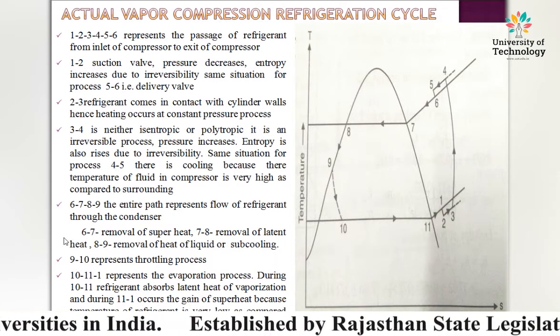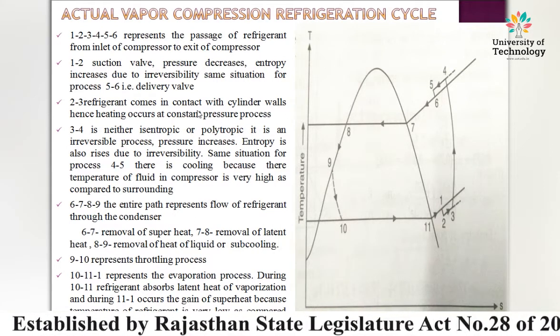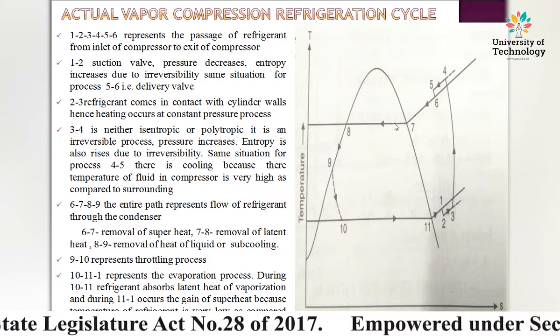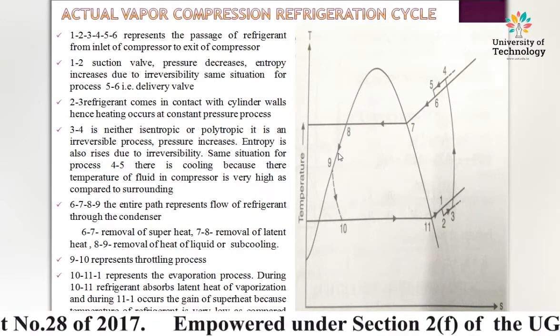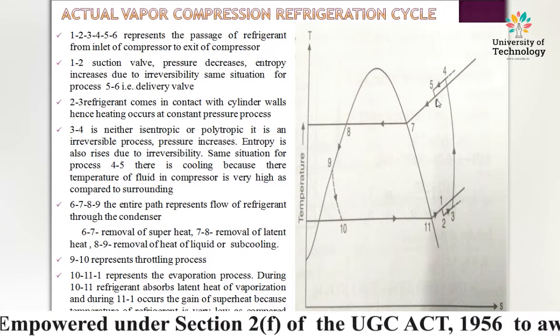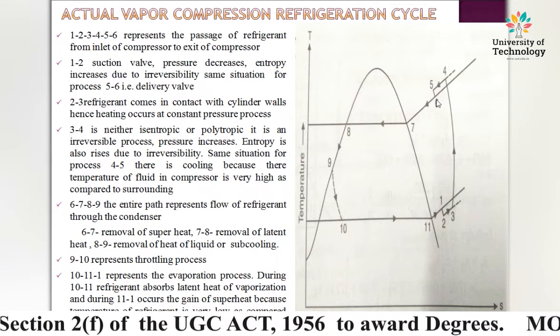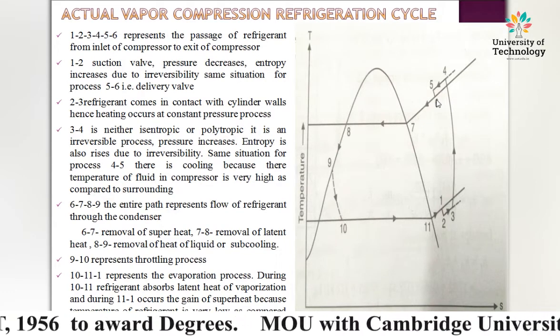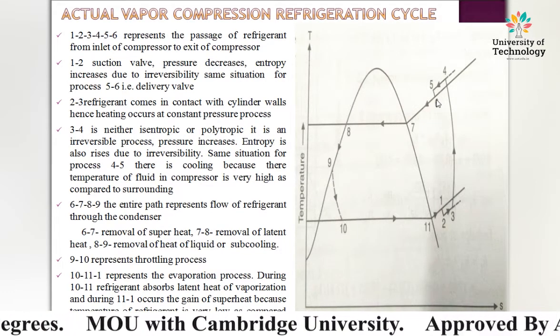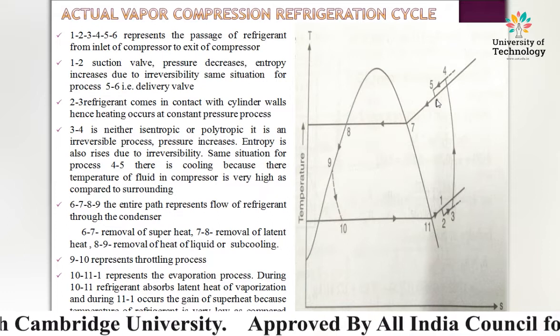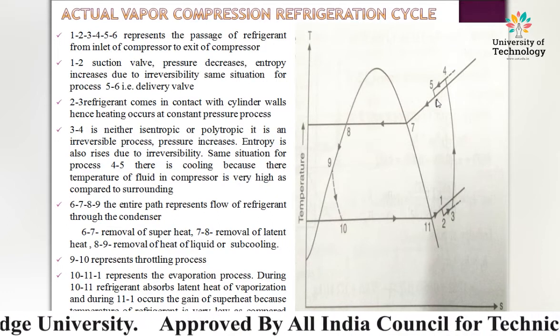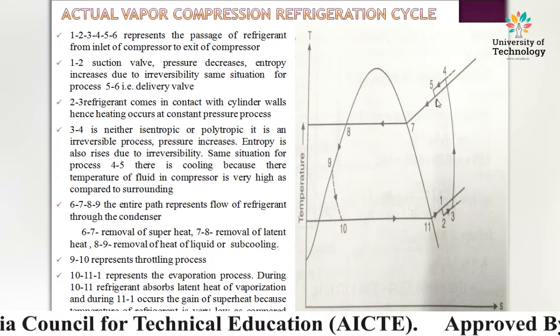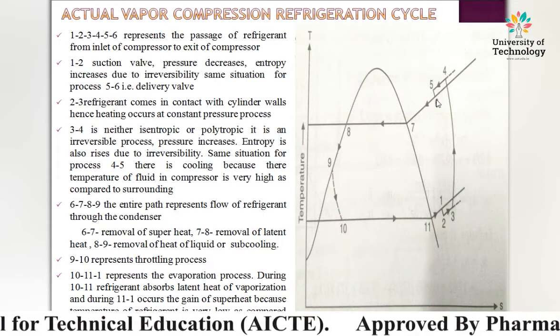Next, points 6-7-8-9 describe the condenser section. At point 6, there is superheated refrigerant. From 6→7, the superheat is removed due to the temperature difference between the system and surroundings — this is the desuperheating process.